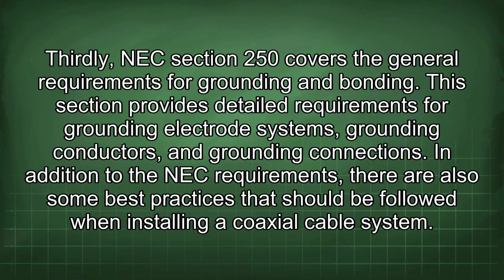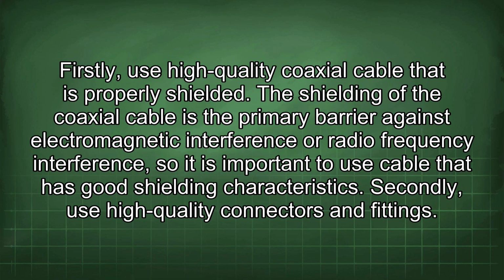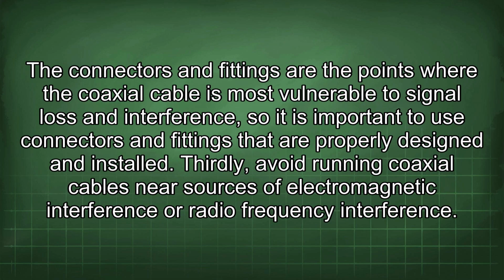In addition to the NEC requirements, there are also some best practices that should be followed when installing a coaxial cable system. Firstly, use high-quality coaxial cable that is properly shielded. The shielding of the coaxial cable is the primary barrier against electromagnetic interference or radio frequency interference, so it is important to use cable that has good shielding characteristics. Secondly, use high-quality connectors and fittings. The connectors and fittings are the points where the coaxial cable is most vulnerable to signal loss and interference, so it is important to use connectors and fittings that are properly designed and installed.